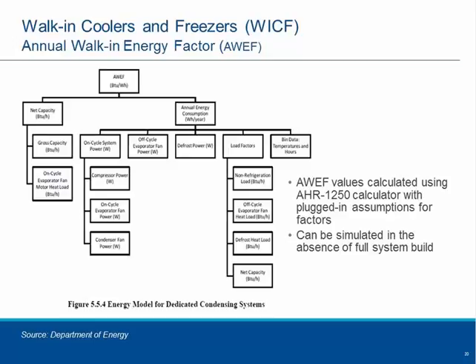This AWEF that we're talking about, it's a new performance standard and it applies to condensing units. It applies to unit coolers or evaporators, panels, and doors. And the minimum efficiency levels are different requirements for medium temp coolers or low temp freezers, and depending on whether the condensing units are located indoors or sometimes are located outdoors.